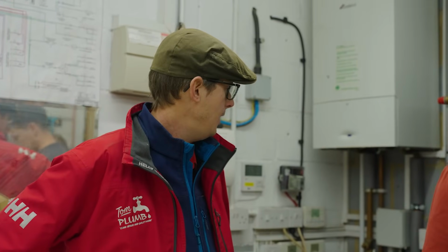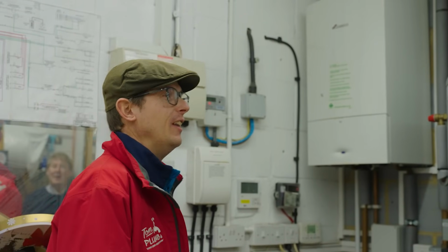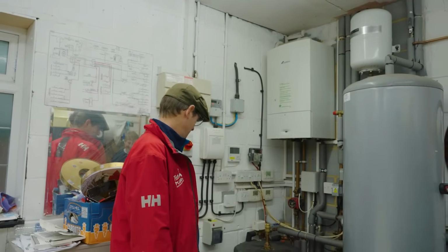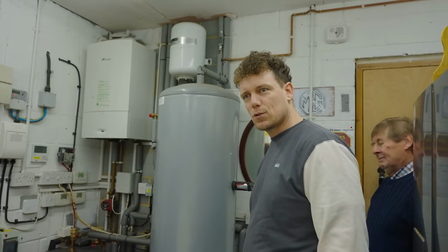Okay. What are your initial thoughts, Tom? It looks pretty good, ready for go, I think. I think the house feels nice and warm. I know the boiler's on and whatnot, but any weather is something. Any estimates before you do the heat loss? No, I've not thought, to be honest. Yeah, it's going to be 12.91 kilowatts. Exactly that number.